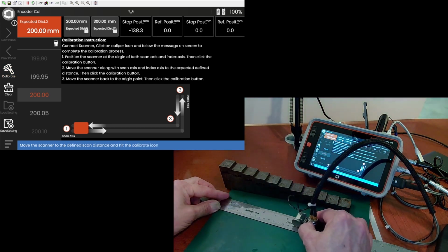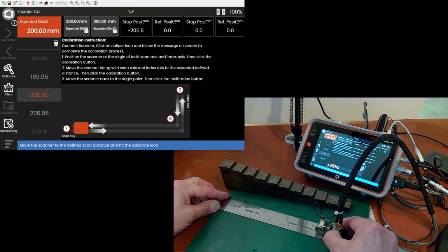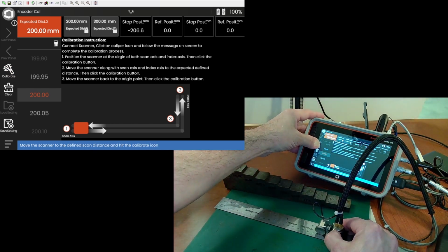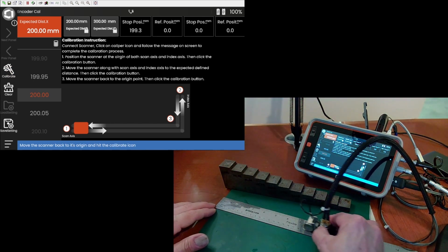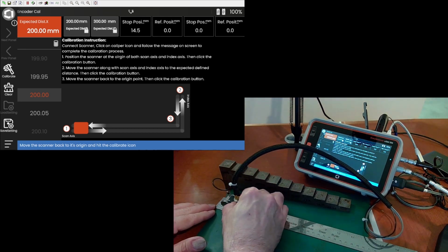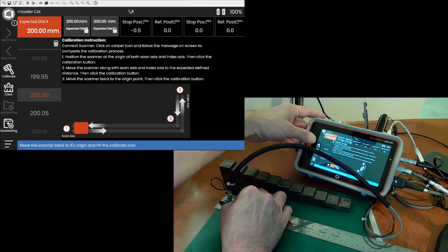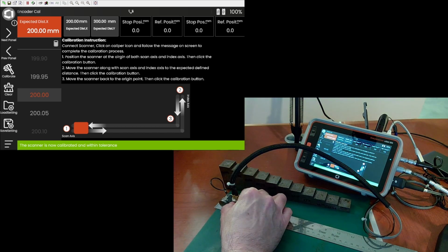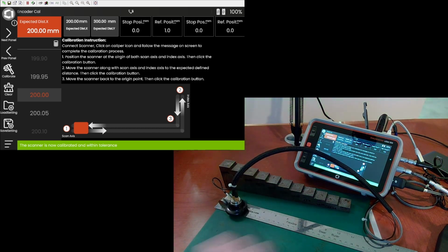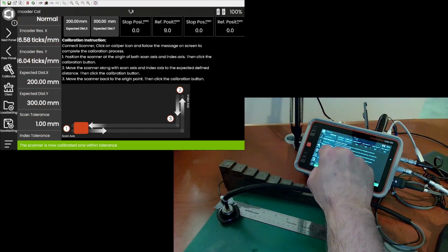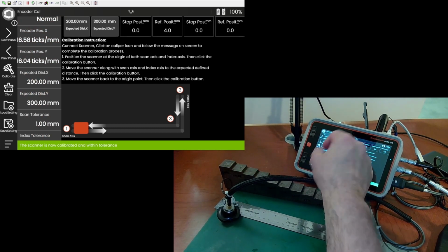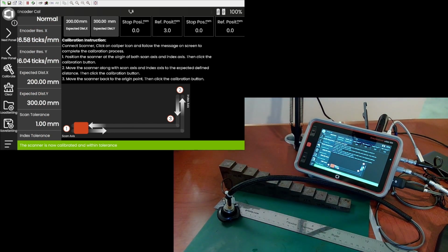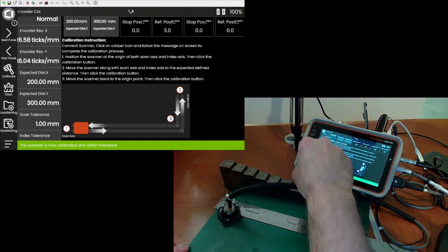We'll move our wheel to 200. Hit calibrate. Move it back to 0. And the encoder is now calibrated. Okay. So if we look, the ticks per millimeter are slightly different than they were before. It went from 6.04 to 6.58, but the encoder is now calibrated.